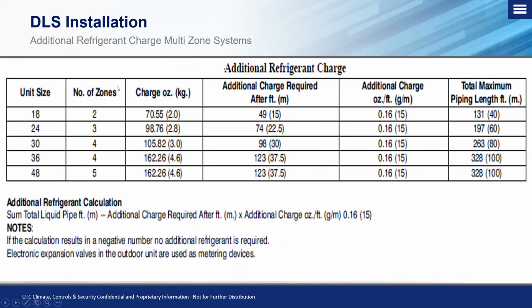Now, as you can see on here, you have 3 zones. Additional charge is required at 74. 4 zones, additional charge is required after 98. So as we increase in tonnage, we'll also increase the amount that we have before we start adding additional charge. You can see on here, the multi-zones are nice because they use that 0.16 ounces per foot for all of them, for the ounces per foot additional charge multiplier. And then your total maximum piping length, again, will depend on the tonnage that you have at your outdoor unit. So this is how we go about dealing with the multi-zones.